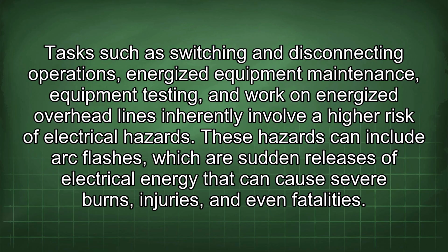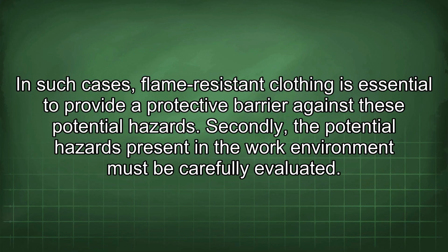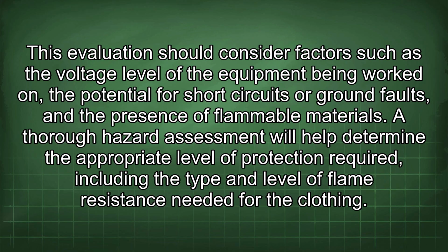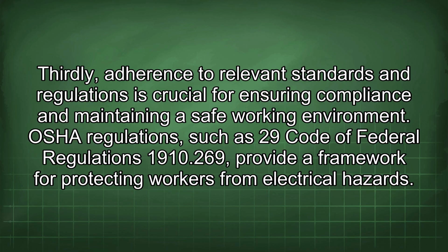These hazards can include arc flashes, which are sudden releases of electrical energy that can cause severe burns, injuries, and even fatalities. In such cases, flame-resistant clothing is essential to provide a protective barrier against these potential hazards. Secondly, the potential hazards present in the work environment must be carefully evaluated. This evaluation should consider factors such as the voltage level of the equipment being worked on, the potential for short circuits or ground faults, and the presence of flammable materials. A thorough hazard assessment will help determine the appropriate level of protection required, including the type and level of flame resistance needed for the clothing. Thirdly, adherence to relevant standards and regulations is crucial for ensuring compliance and maintaining a safe working environment.